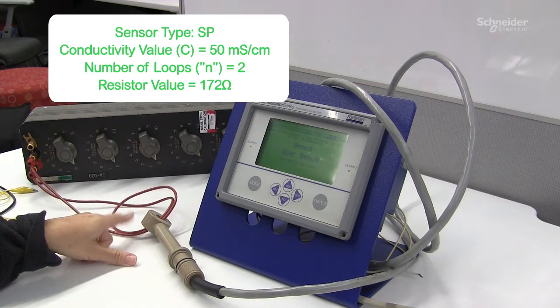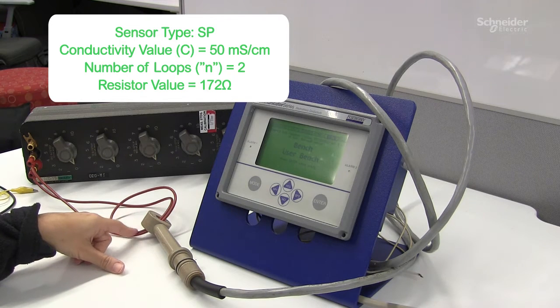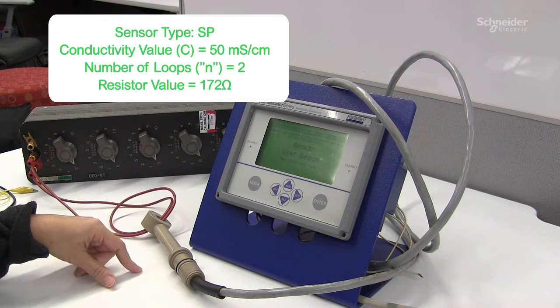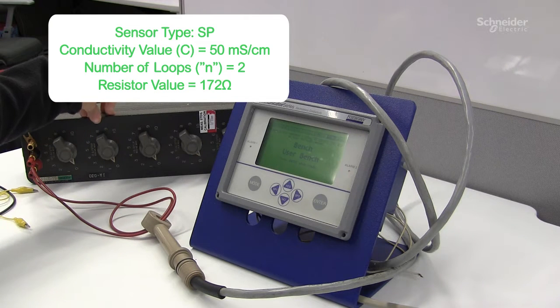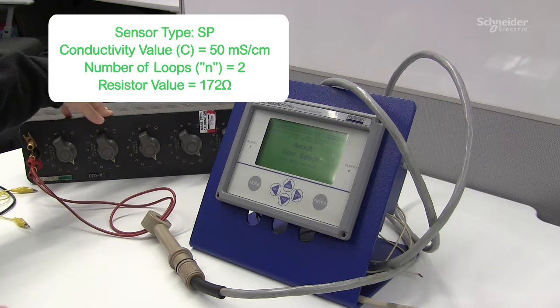Doing this type of connection, in my formula number of loops equals to two. To replicate or simulate 50 millisiemens, I will need to dial 172 ohms. So now I'm above 100 and I can use that value.